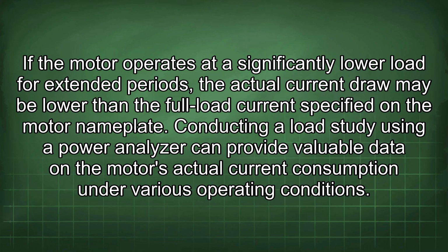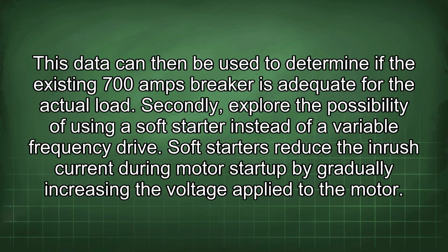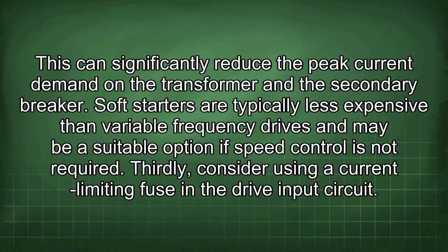Conducting a load study using a power analyzer can provide valuable data on the motor's actual current consumption under various operating conditions. This data can then be used to determine if the existing 700 amps breaker is adequate for the actual load. Secondly, explore the possibility of using a soft starter instead of a variable frequency drive. Soft starters reduce the inrush current during motor startup by gradually increasing the voltage applied to the motor. This can significantly reduce the peak current demand in the transformer and the secondary breaker.